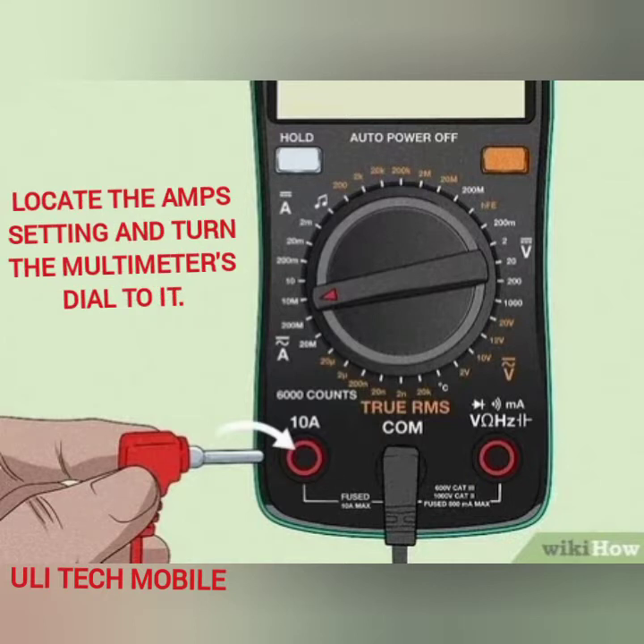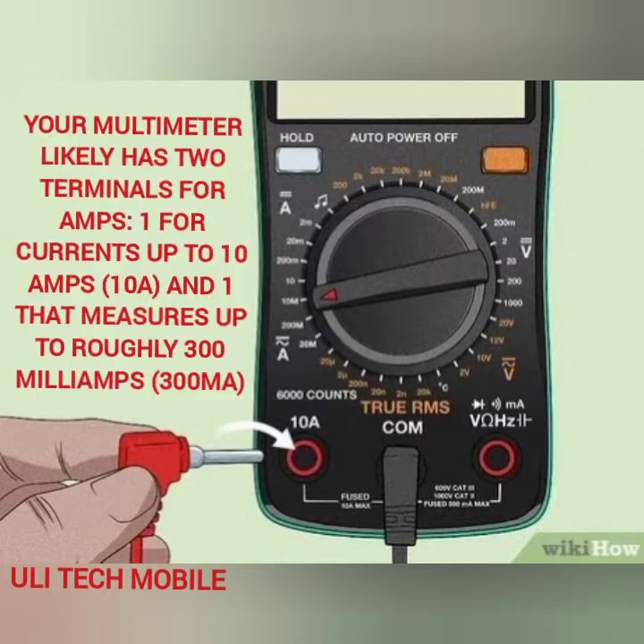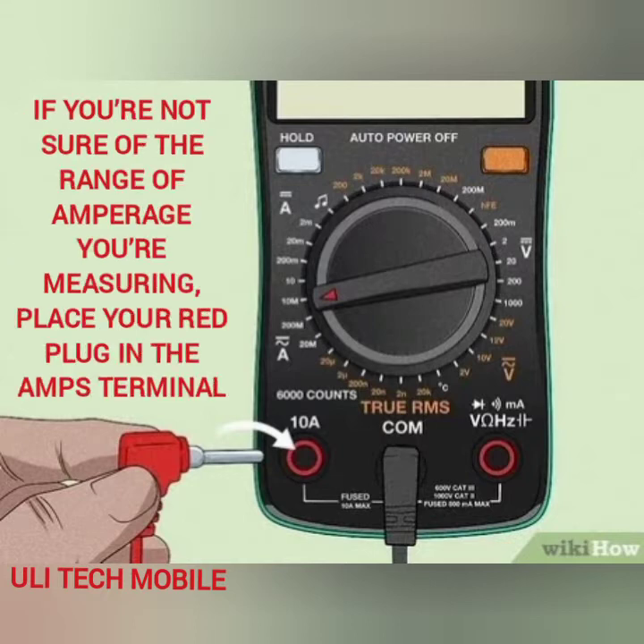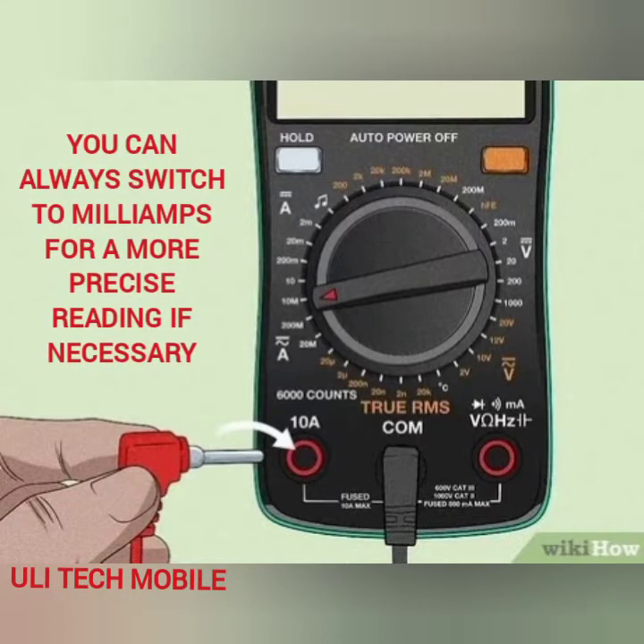Locate the amp setting and turn the multimeter dial to it. Your multimeter likely has two terminals for amps, one for current up to 10 amps, and the other to measure up to roughly 300 milliamps. If you are not sure of the range of amperage you are measuring, place your red plug on the amps terminal. You can always switch to milliamps for a more precise reading if necessary.